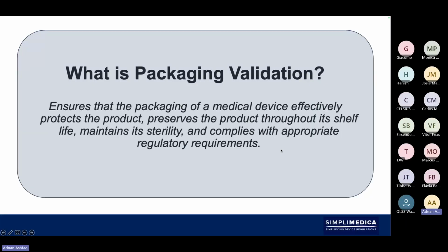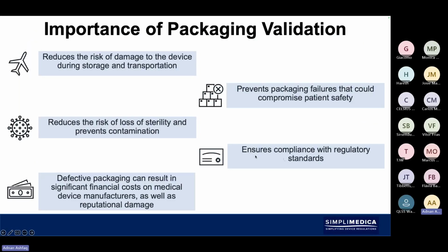So let's start off with what packaging validation is. Packaging validation can be defined in many different ways, but essentially what we're looking to do in packaging validation is ensure that the packaging of the medical device is effectively protecting the product, is preserving the product throughout its shelf life, is maintaining its sterility, that's of course if it's sterile, and of course complies with appropriate regulatory requirements.